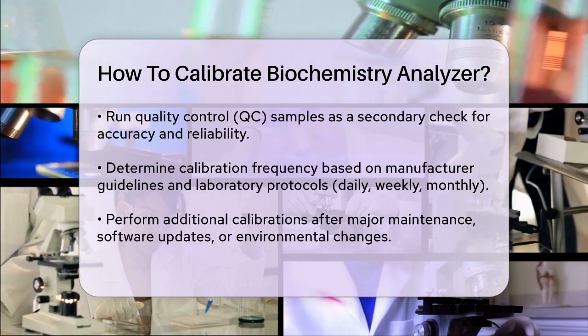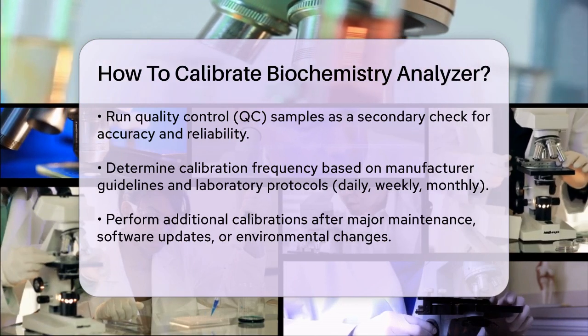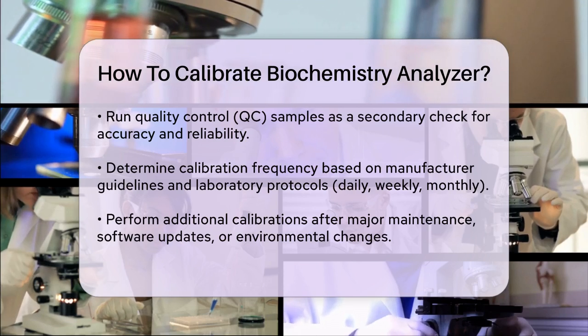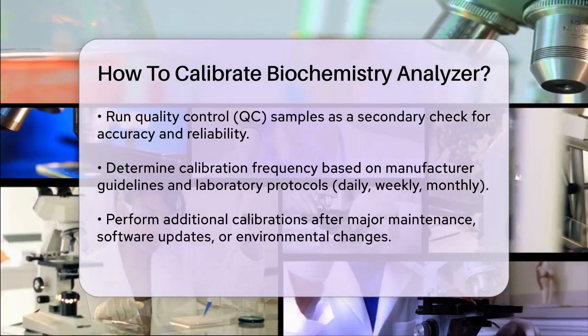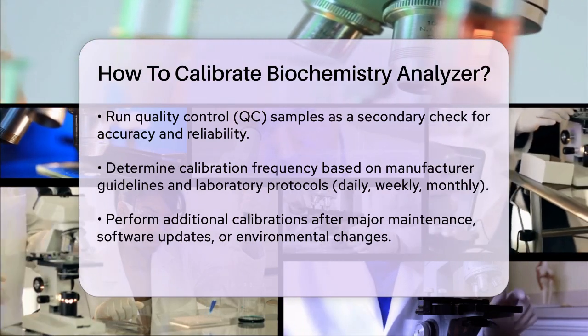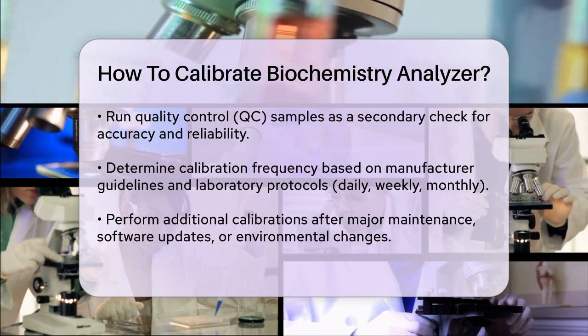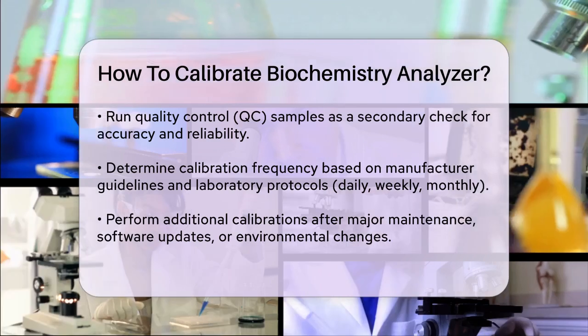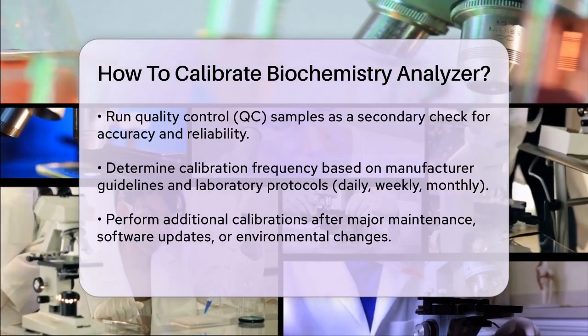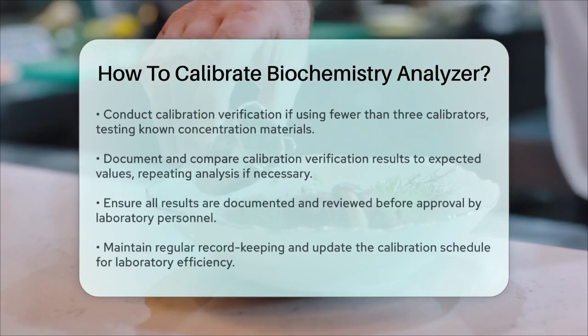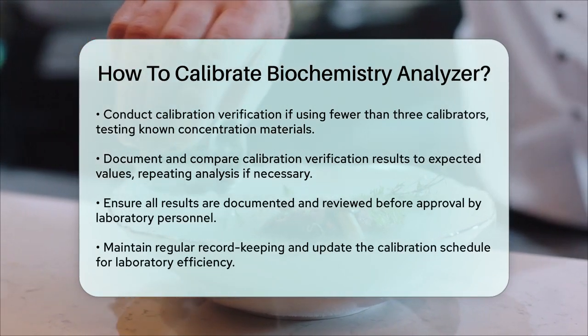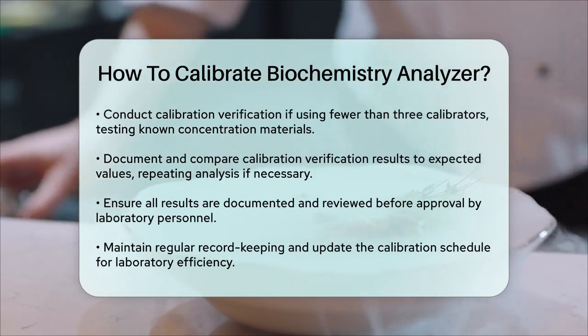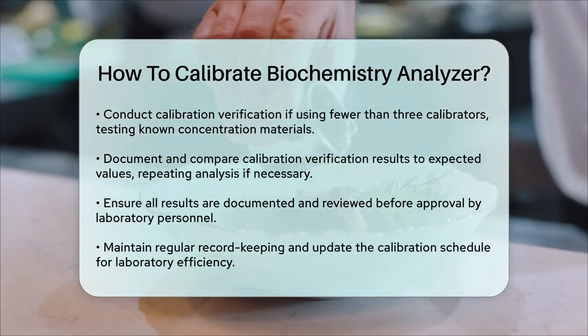Calibration verification is another important aspect, especially if you're using fewer than three calibrators for routine calibration. This process involves testing materials of known concentration in the same manner as patient specimens to ensure the test system accurately measures samples throughout the reportable range. This verification is usually required every six months, or more frequently if indicated by the manufacturer or the laboratory. When performing calibration verification, use materials such as calibrators from a different lot, commercially available materials, or primary or secondary standards with known concentrations. Compare the results to expected values and document them. If the results show non-linear calibration, you may need to repeat the analysis according to your laboratory's established criteria.